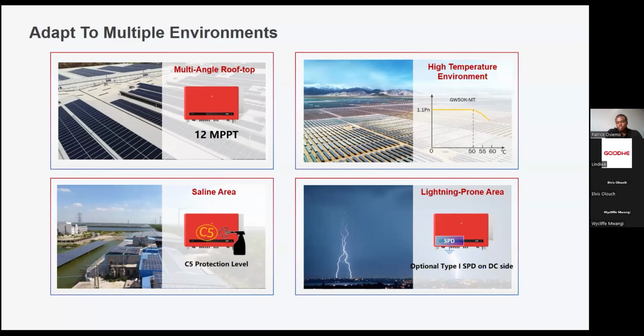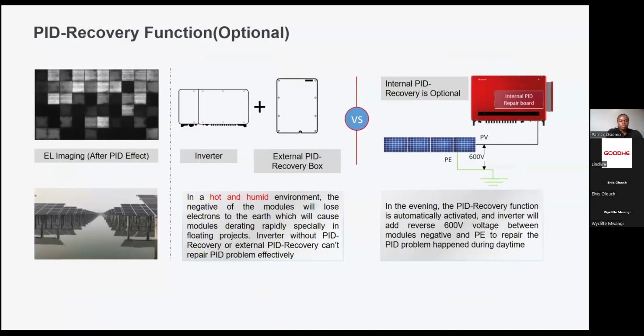I mentioned the type 2, type 3 installations, SPDs installed on our PV side and our AC side. So yes, your system is already protected with SPDs on the DC and on the AC side, ensuring your system is quite safe and reliable. For installations done near coastlines with high humidity, high saline conditions, the SMT and the HT series inverters come with the PID integrated recovery.